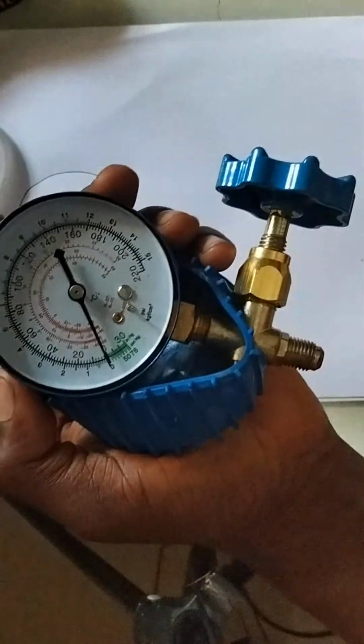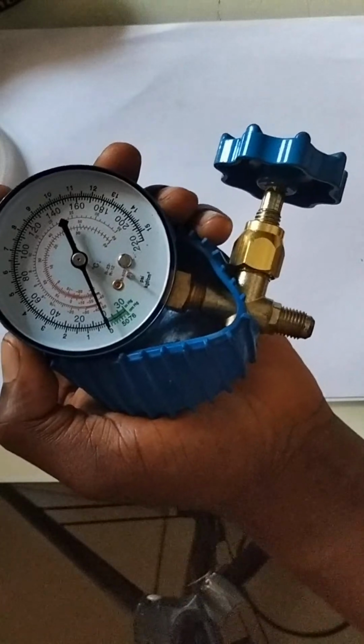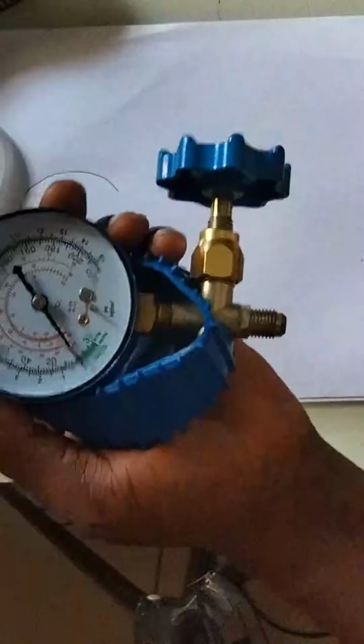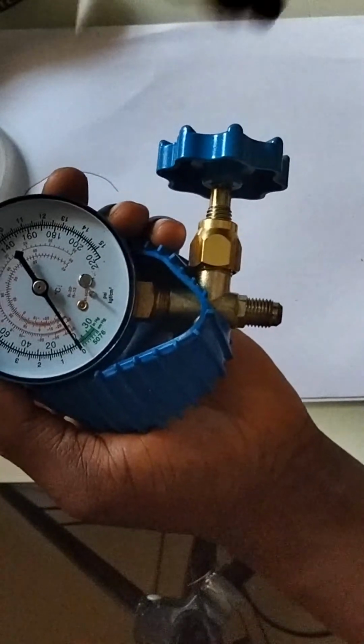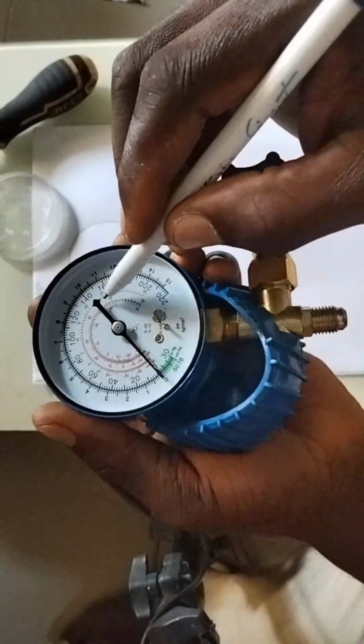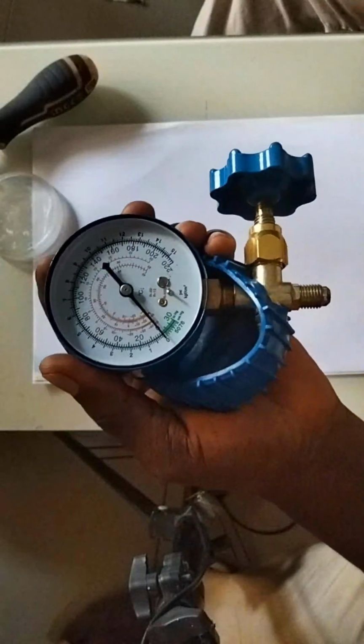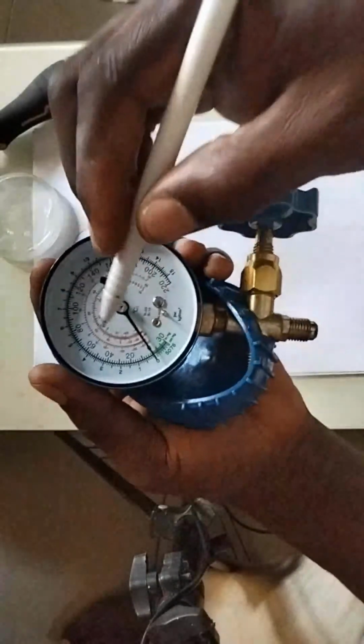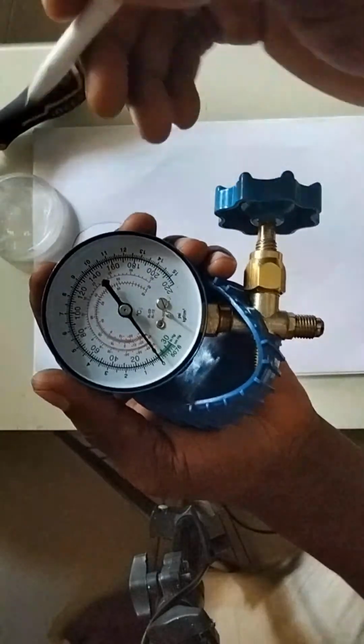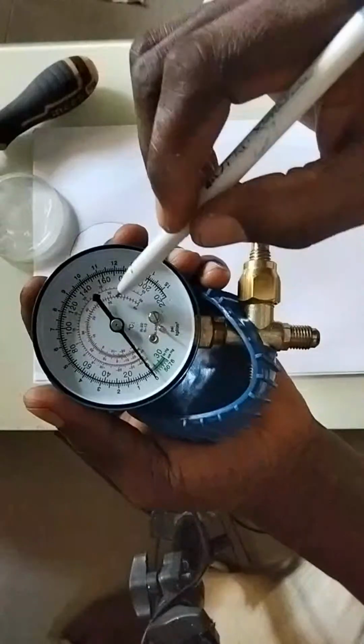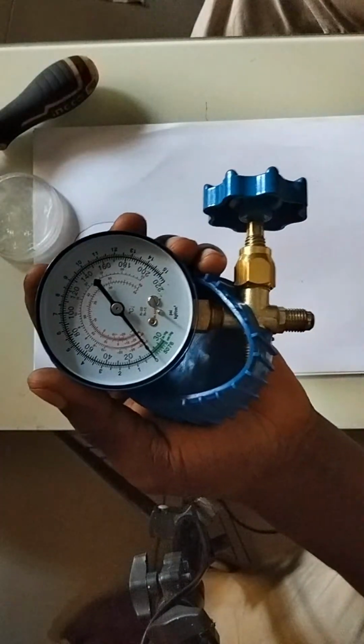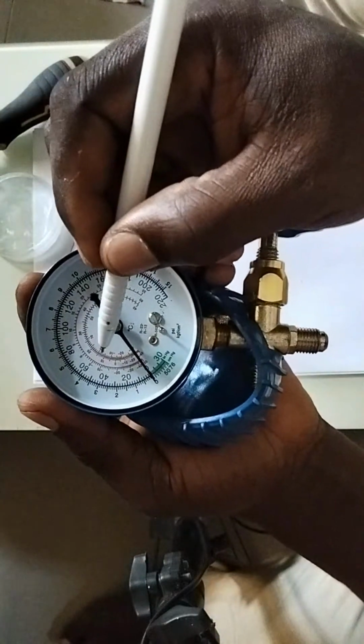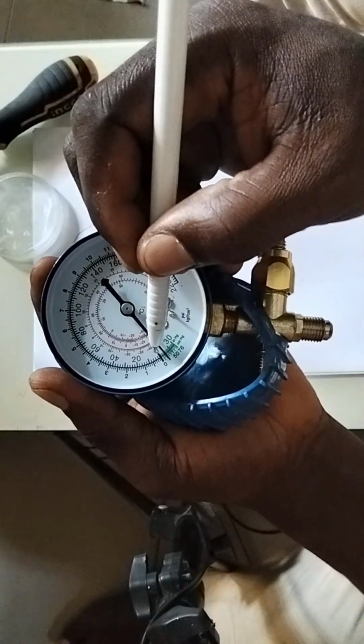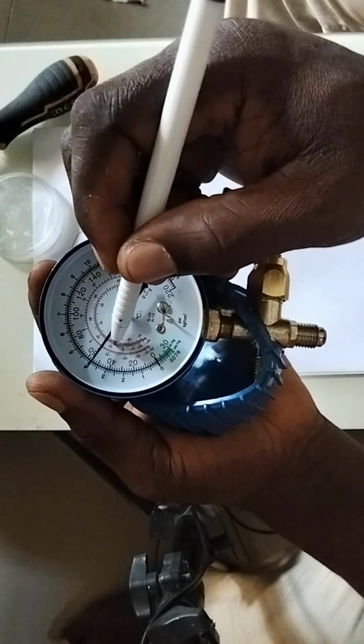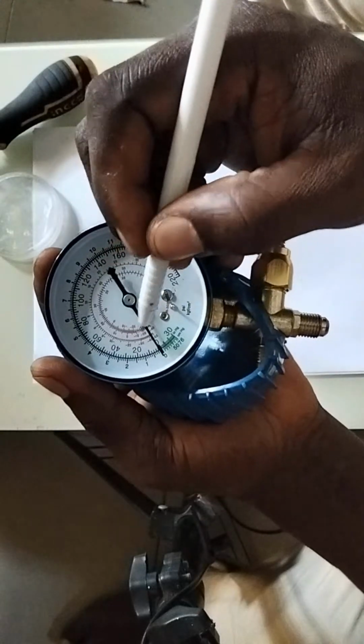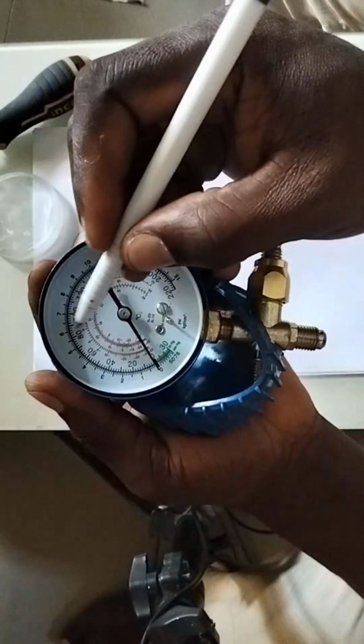Now, how do you know that you are actually on the right track? The heat that you feel coming out of the outdoor unit is due to the refrigerant's boiling point. You get me right? This is the scale, and this is the point where you can notice the boiling point of a particular refrigerant. Now, why I had to leave R410 is that its boiling point is not on this scale. Understand? Now let's use R22 for example. If you charge R22 from 0 psi up to 60 psi, as R22 is always 60 psi, this is how to notice the boiling point of R22.